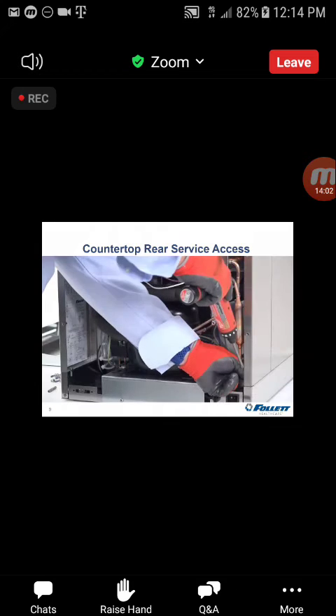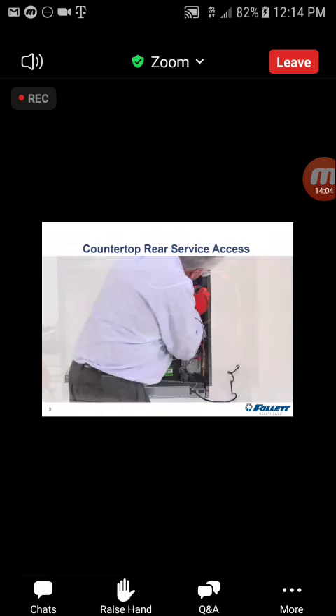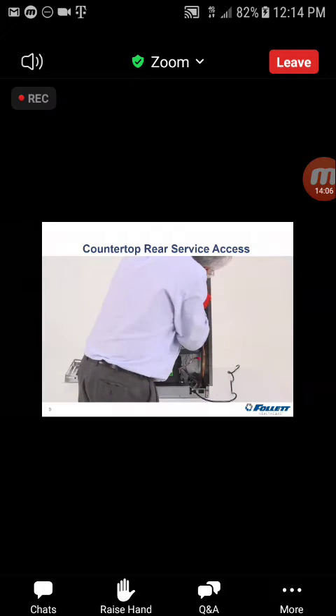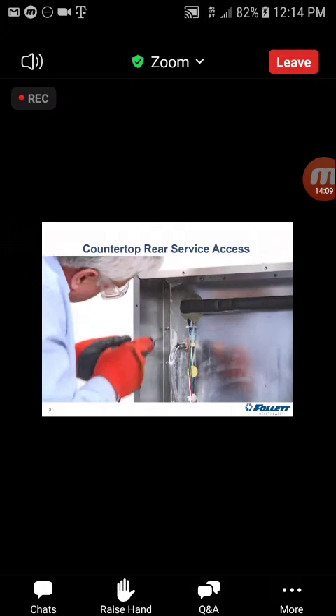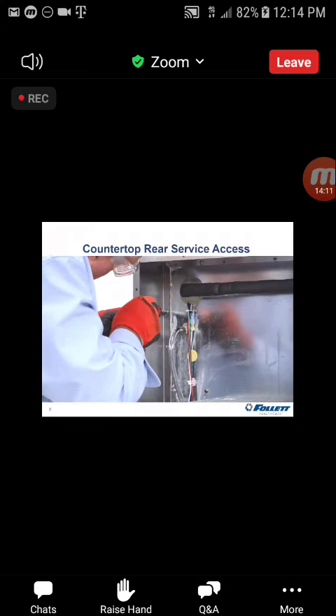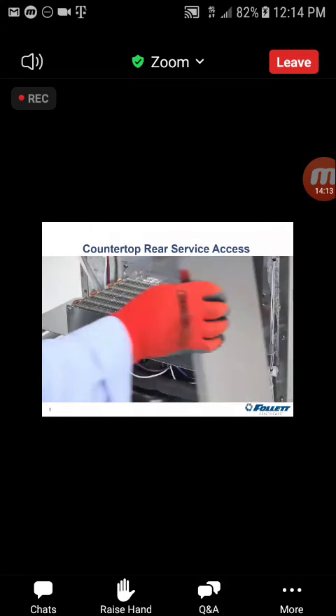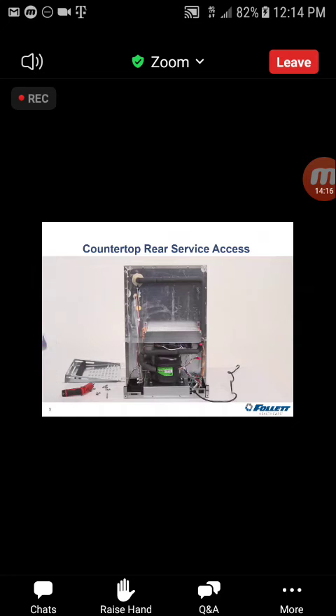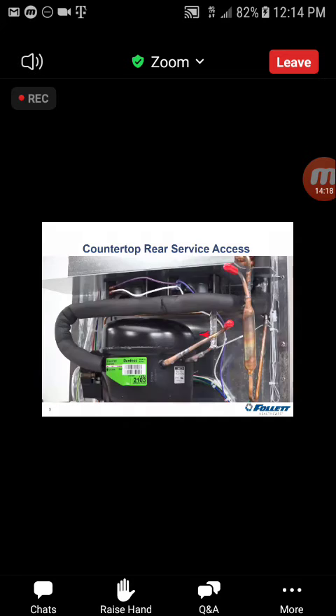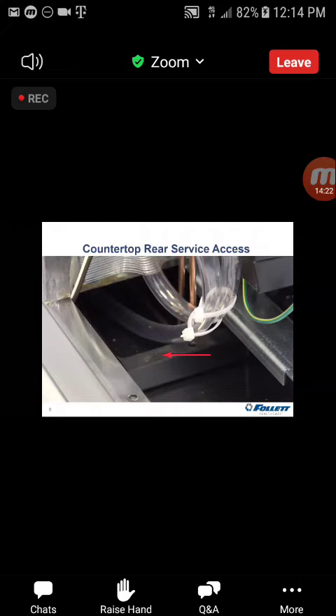To remove the wrap, there are 2 vertical Phillips head screws that need to be removed. Then there are 6 Phillips head screws that only need to be loosened, 2 on each side, 2 at the top. Once the screws are loosened, the wrap can be lifted up and off of the unit. Removing the lower service panel and the wrap will give you access to the compressor, the condenser fan motors, and the condensate pan on the left-hand side of the unit. So that was the countertop unit. The next thing we're going to be looking at is the rear service access of the under-counter unit.